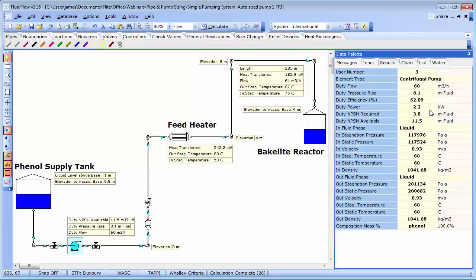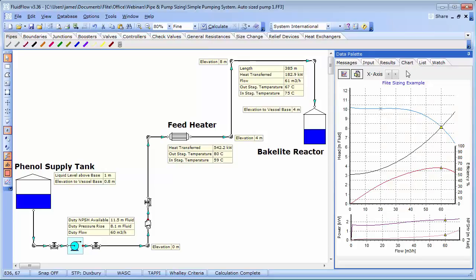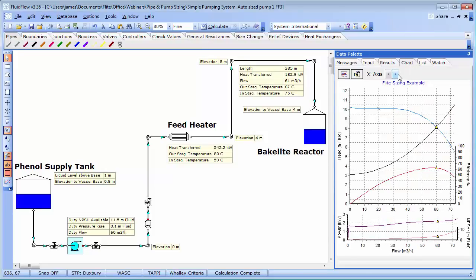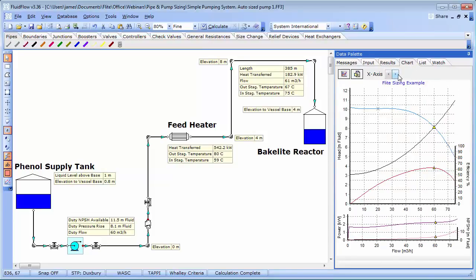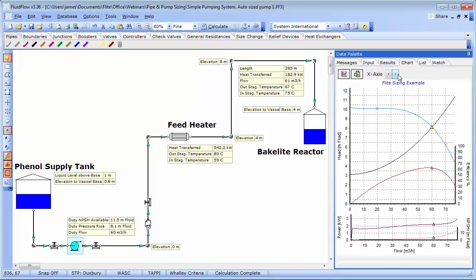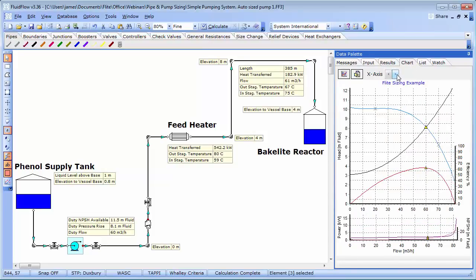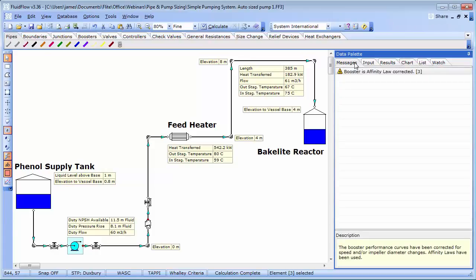We can also make a quick check on the NPSH conditions confirms that we are still within the safe operating limits for the pump. We can also make a quick check on the pump curves to review the performance. You may also notice that we have a warning message. This is just letting us know that the booster affinity laws have been applied since we have changed the pump operating speed.